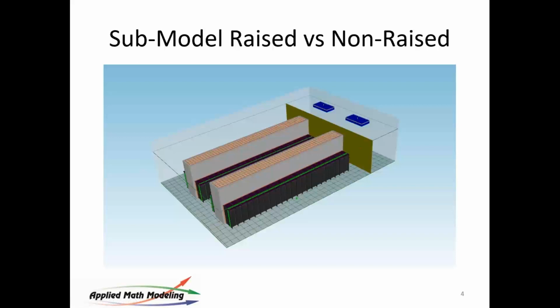And the simple thought is, if we flood the room with cold air, there's enough volume there, so everything should be good. And we contain the hot side, as you can see here, and all the hot air goes back up into the ceiling plenum. Everything's good, right? We don't need to run CFD on this. This is what I often hear. We don't need to model this. Everything's perfect. Not so much.